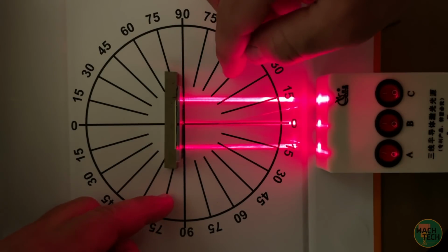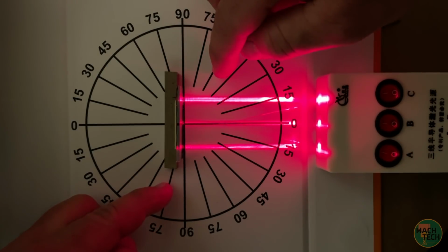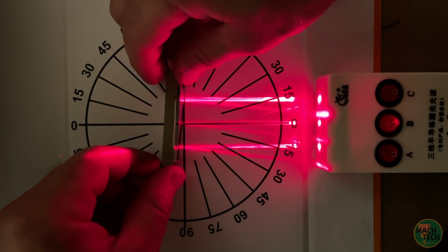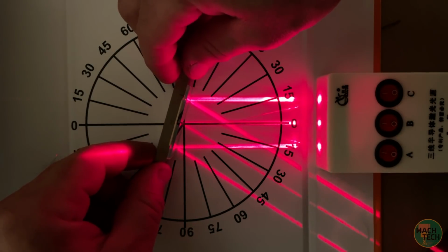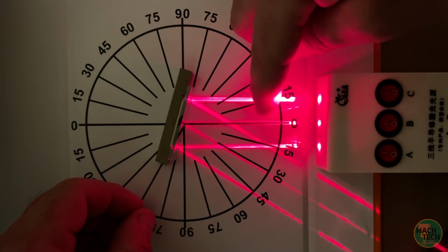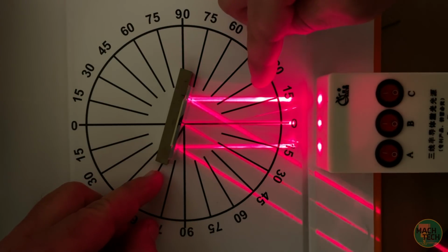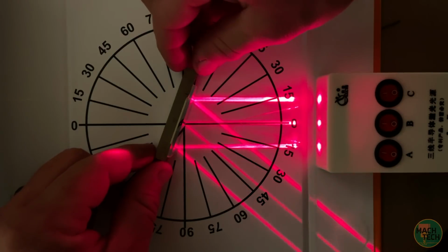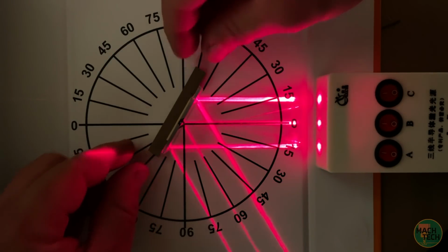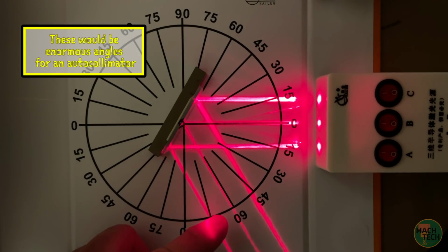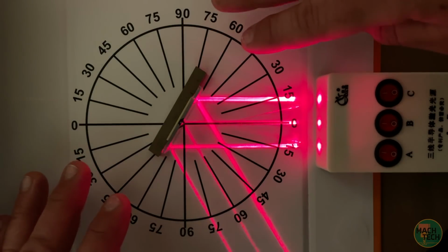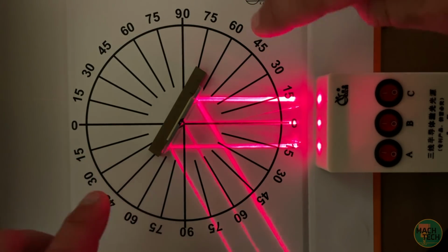What this means for us and our quest to understand the inner workings of autocollimators is that collimated light coming out of the autocollimator will be reflected back into the autocollimator at exactly twice the angle of the mirror relative to the collimated rays. If the angle of the mirror is at 15 degrees, then the angle of the reflected ray will be 30 degrees. And if the angle of the mirror is 30 degrees, then the angle of the reflected ray will be 60 degrees, and so on. Okay, I hope that that clears up the 2 theta issue, but now we have to talk about lens focal length.